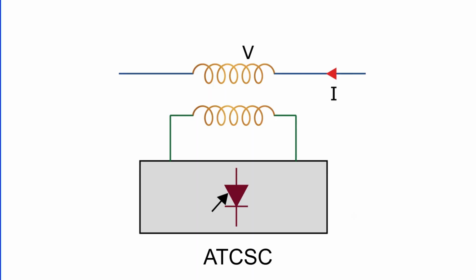Now let us move to another important FACTS device called Advanced Thyristor Controlled Series Compensation, or ATCSC. You can see the arrangement on the screen. The concept here is somewhat similar to improving an SVC into a STATCON using GTO technology. In the same way, a controlled series compensator can be upgraded into ATCSC using a voltage-driven GTO converter. In this system, the GTO converter is connected in series with the transmission line.